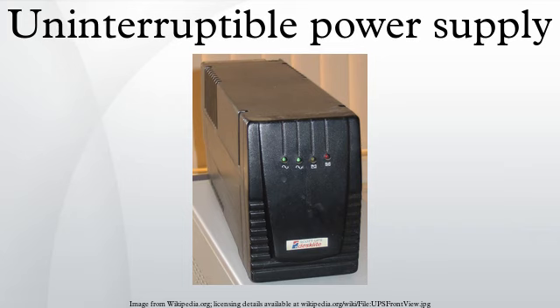This configuration is also referred to as 1+1 or 2N redundancy. If the budget does not allow for two identical UPS units, then it is common practice to plug one power supply into mains power and the other into the UPS.